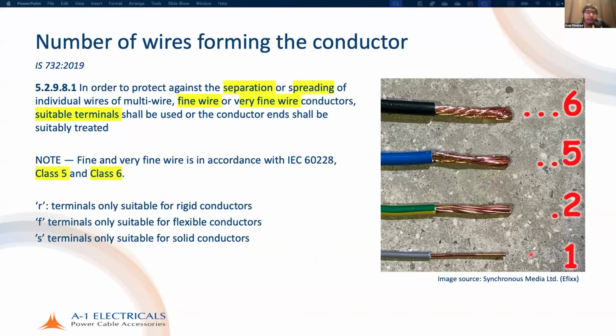When we talk about the number of wires forming the conductor, this is very important. The standard says that in order to protect against the separation or spreading of individual wires of multi-wire, fine wire, or very fine wire conductors, suitable terminals shall be used or the conductor end shall be suitably treated. Now, fine and very fine wires in accordance with IEC 60228, which is the standard for conductors, are very important here. There is class 1, which is solid, class 2, which is stranded, class 5, which is fine stranded, and class 6, which is very fine stranded.